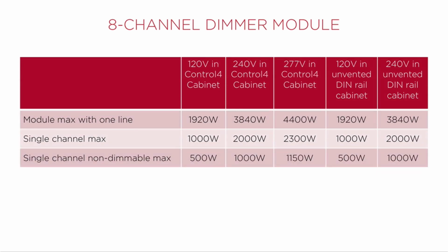Here are the maximum wattages for the Control4 dimmer module. At 120 volts, in a Control4 cabinet, the maximum with one line is 1,920 watts. There is a maximum of 1,000 watts per single channel, and if connected to a non-dimmable load, a 500 watt maximum per single channel. Those numbers double if used with 240 volts, and those numbers remain the same for 120 and 240 volts if used in a non-Control4 unvented DIN rail cabinet.